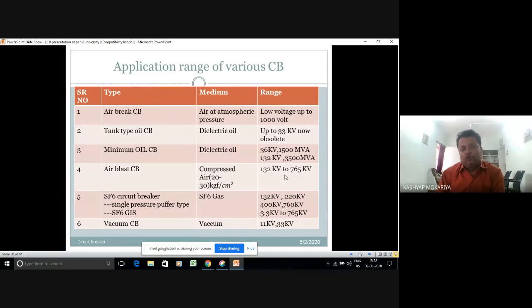I am showing just a rating to you. This is an application, air break circuit breaker. See, here it is written, it is used up to a low voltage of 1000 volt. But in many industries which I visited, even after completing my master's, I normally found air circuit breakers in most of the industries up to 415 volt. So in industry, you will be dealing with an air circuit breaker which is operated for low tension motors, operated on 415 volt, and the rating of the machine is somewhere between 90 kilowatt to 160 kilowatt. For that, this type of breaker is used.